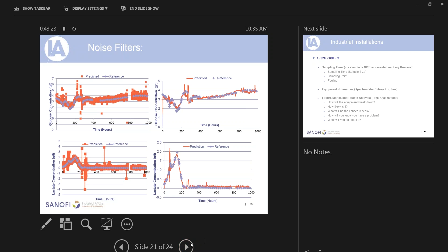influencing the data. So what we did here was we used nonlinear filters to clean up the signal, and you can see then on the right-hand side, the clean signal follows the reference values much more closely. And so we take a system that's barely capable of measuring the thing that we're interested in and extract from that noisy signal a fairly reasonable approximation of the truth. So not all the problems have to be solved with the spectrometer. You can solve these downstream with the PLS or with noise filters afterwards.